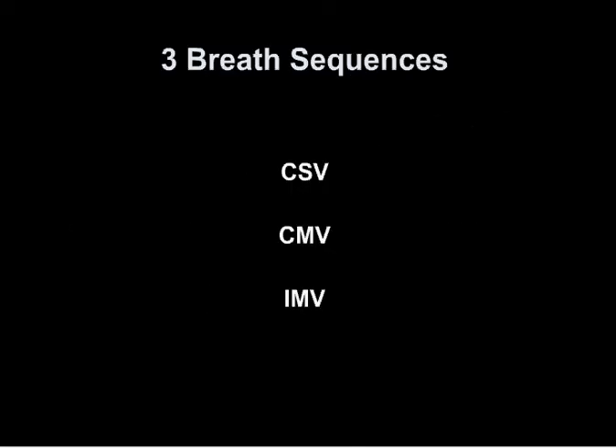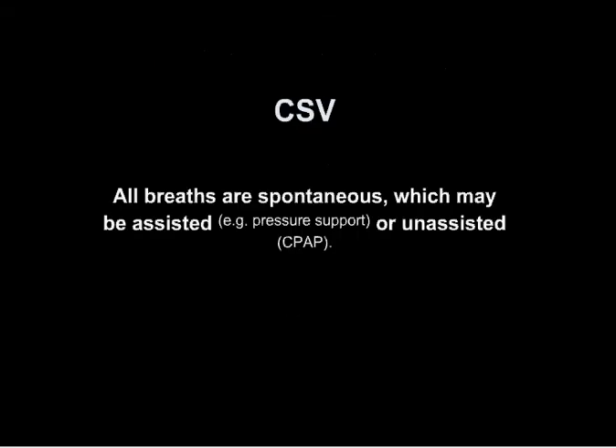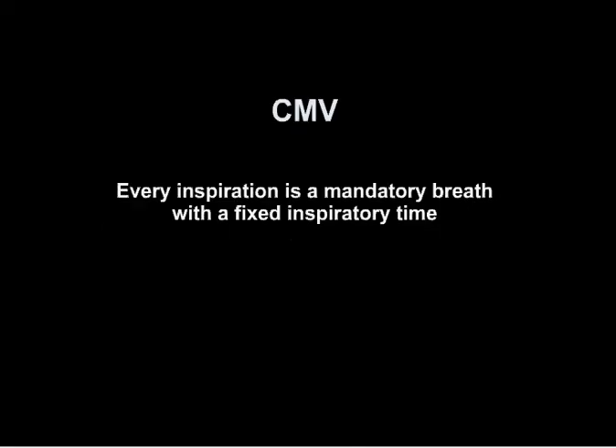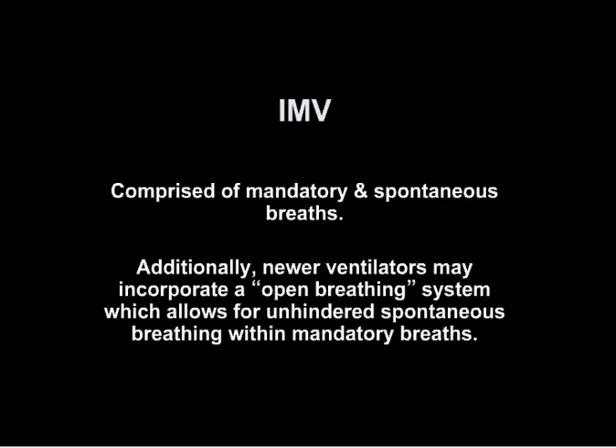There are three breath sequences: continuous spontaneous ventilation (CSV), continuous mandatory ventilation (CMV), and intermittent mandatory ventilation (IMV). With CSV, all breaths are spontaneous, which may be assisted or unassisted. With CMV, every inspiration is a mandatory breath with a fixed inspiratory time. With IMV, breaths are comprised of mandatory and spontaneous breaths. Additionally, newer ventilators may incorporate an open breathing system which allows for unhindered spontaneous breathing within mandatory breaths.